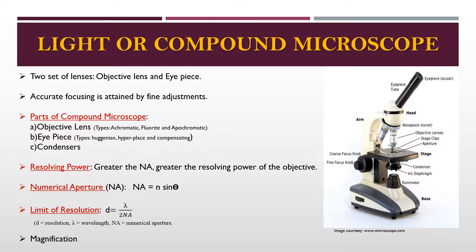The limit of resolution is defined as the smallest distance between two separate objects that can be distinguished as two separate objects. Greater resolution in a light microscope is obtained with the shortest wavelength of visible light and an objective with maximum numerical aperture. The formula is: Resolution = wavelength / (2 × NA). Magnification of the microscope is the increase in size of the object, and magnification beyond resolving power has no value.